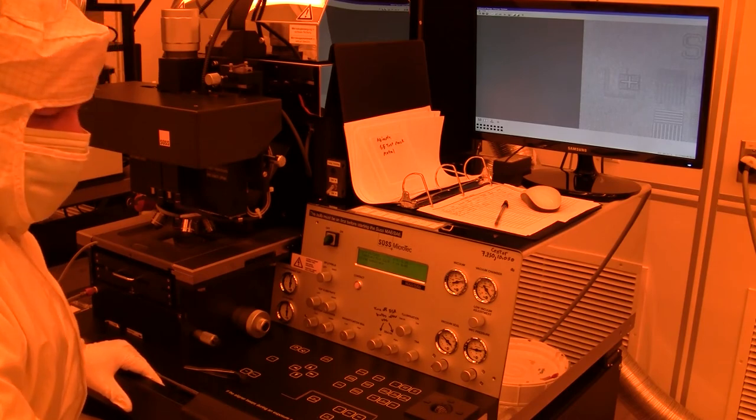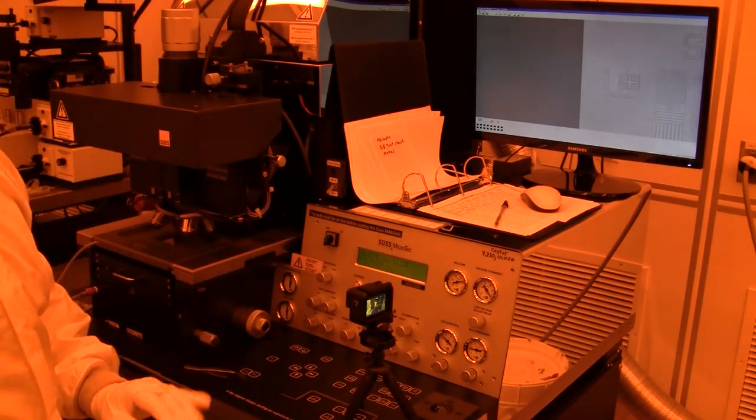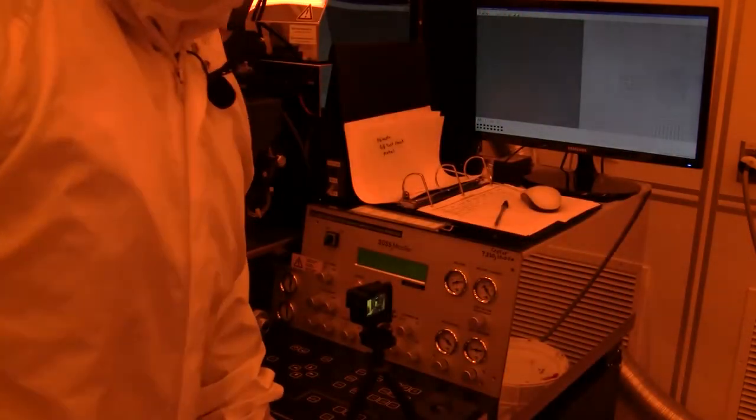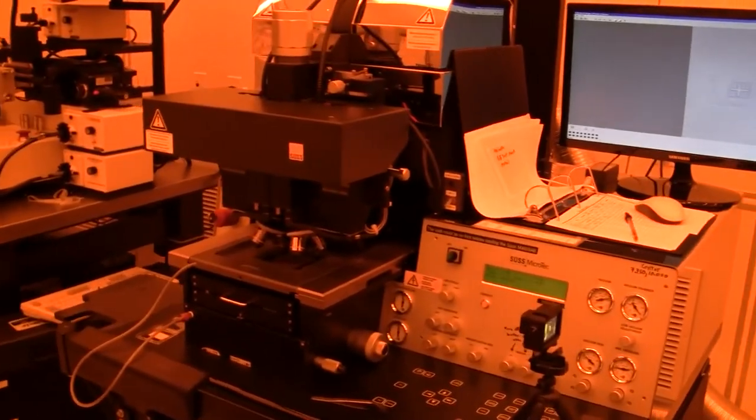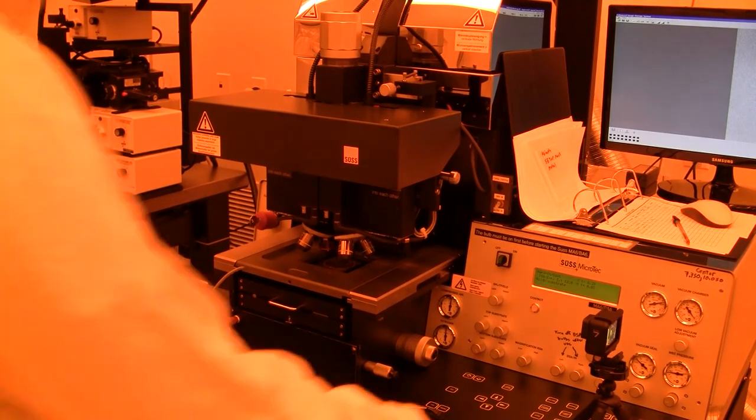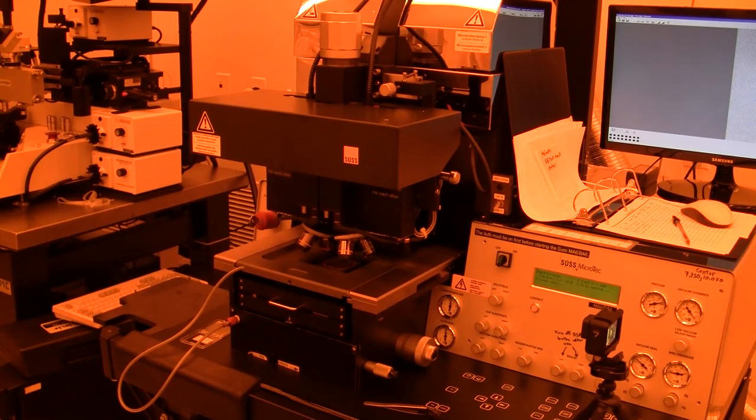So now we are ready to do an exposure, which is kind of cool. Fire away. I press the exposure button. Now the optics will rise up and the lamp housing will move forward and it'll light it up.